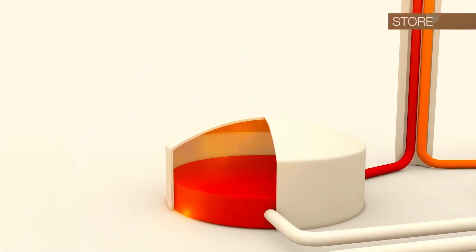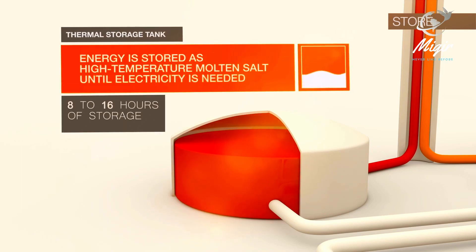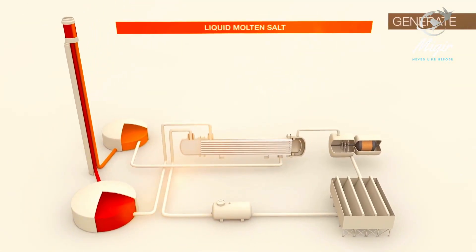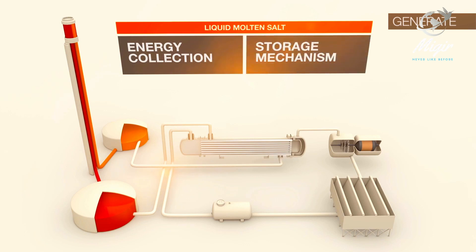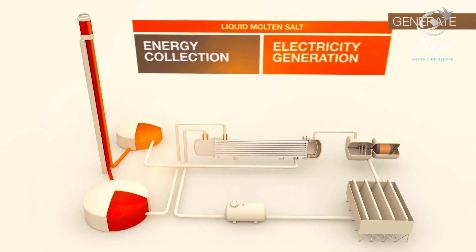After passing through the receiver, the molten salt then flows down the piping inside the tower and into a thermal storage tank, where the energy is stored as high temperature molten salt until electricity is needed. SolarReserve's technology leverages liquid molten salt as both the energy collection and the storage mechanism, which allows it to separate energy collection from electricity generation.